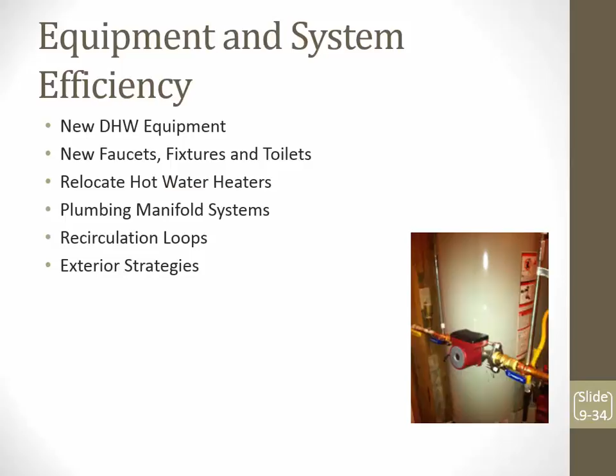But if you're doing a weatherization or whole house energy retrofit, and already replacing the hot water heating equipment, look at options like putting it in a more central location, or using plumbing manifolds where you reduce the line size so you don't have as much hot water standby loss.